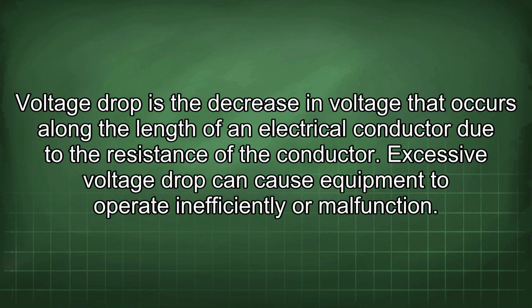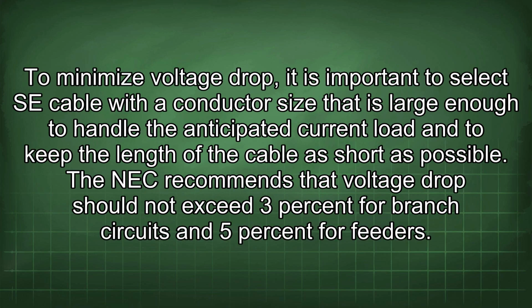Excessive voltage drop can cause equipment to operate inefficiently or malfunction. To minimize voltage drop, it is important to select SE cable with a conductor size that is large enough to handle the anticipated current load and to keep the length of the cable as short as possible. The NEC recommends that voltage drop should not exceed 3% for branch circuits and 5% for feeders.